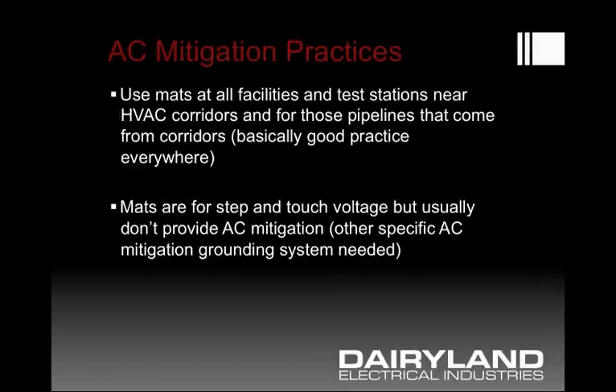AC mitigation practices are to use matting at facilities and test stations near where there could be induced effects or fault effects — so anywhere there would be a high voltage AC corridor. It is also good practice to use mats at any location where there could be overvoltage conditions. They are usually used for step and touch voltage, but they aren't going to be low resistance AC grounds for mitigation. That would come from other grounding systems that one would install specifically for that task.